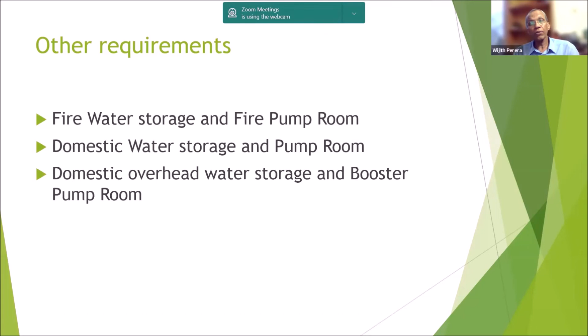I think I should not take too much time. We have a few other requirements like the fire water storage, domestic water storage, domestic overhead water storage and booster pump room, and we need to find space for these. This again has certain restrictions. Fire water storage, for example, very often is pretty large. If you have a sprinkler system, it can be as high as 225 cubic meters, which is a large volume. Or if it is a hose reel system and a landing valve system, it may be something like 65 cubic meters. So we need to find space for this.